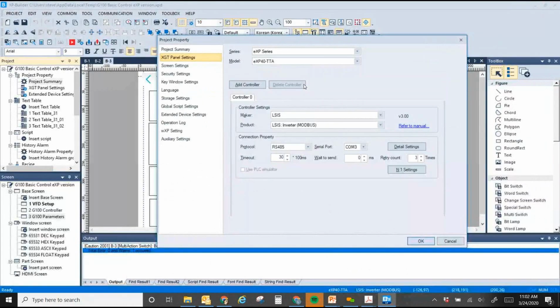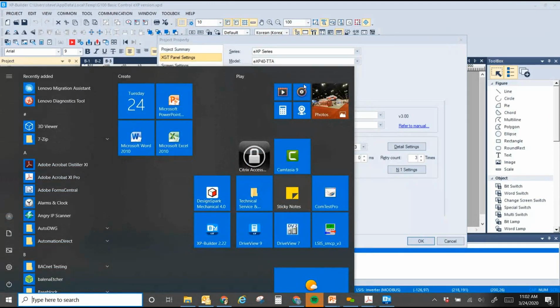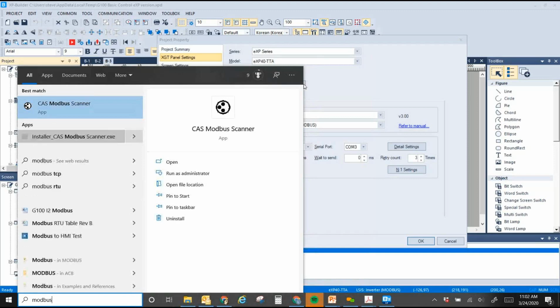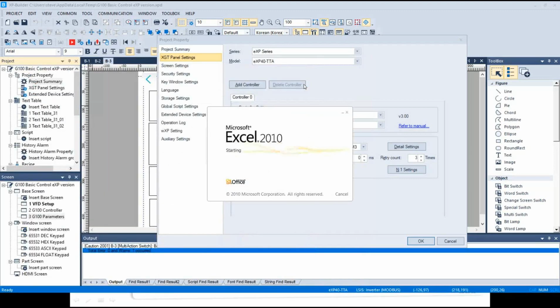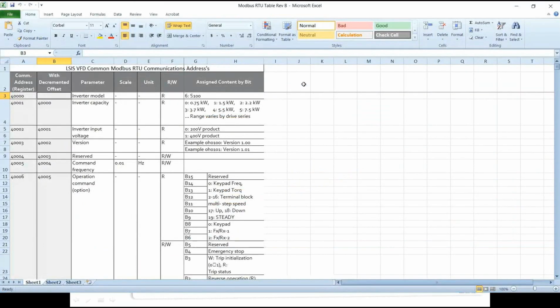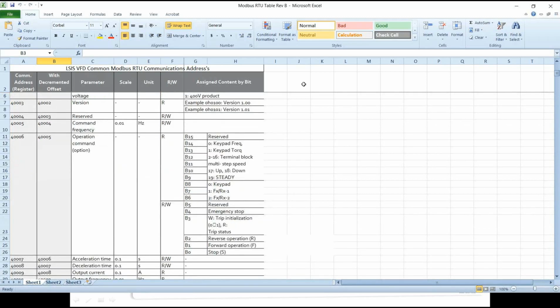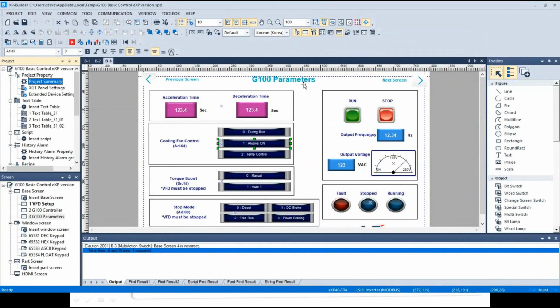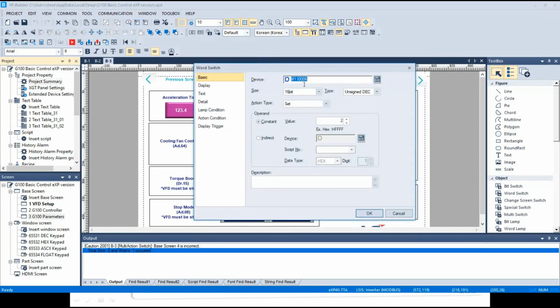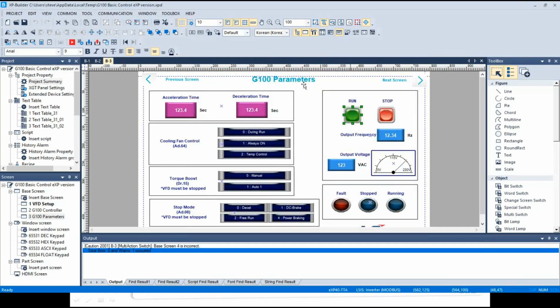But since I'm connecting to an LS drive, I would want to look at the Modbus table, which is something like this. These are all the registers for Modbus for an LS drive. So register 6 is for your operation command. If I close this temporarily and hit my run button, this is set for register 6. So that's how the registers work.